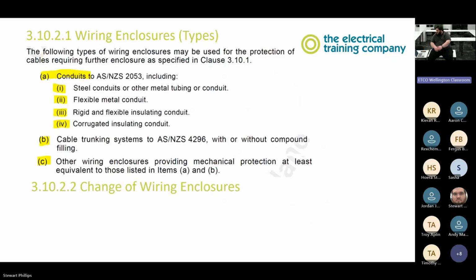Cool. So then we have types of wiring enclosures. The following types of wiring enclosures may be used for protection of cables requiring further enclosure as specified in clause 3.10.1. So steel conduits or other metal tubing, flexible metal conduit, rigid and flexible insulating conduit, corrugated insulating conduit. So those are what we're allowed to use under clause 3.10.1 for separating wiring enclosures. So cable trunking systems to AS/NZS 4296. You can look these up. They are quite boring. With or without compound filling. Other wiring enclosures providing mechanical protection at least equivalent to those listed in A and B.